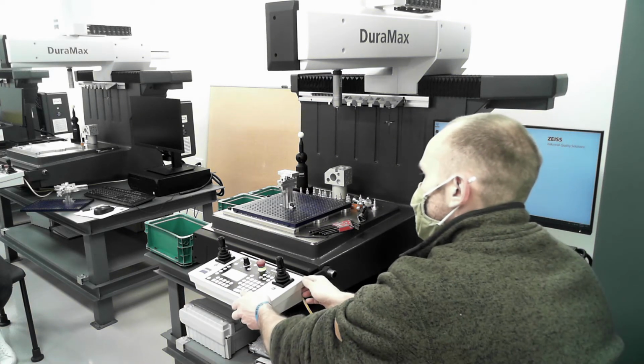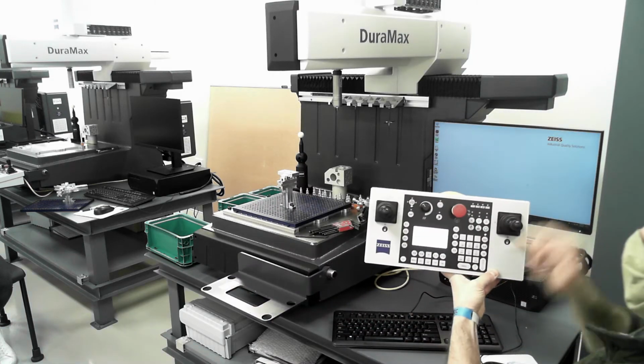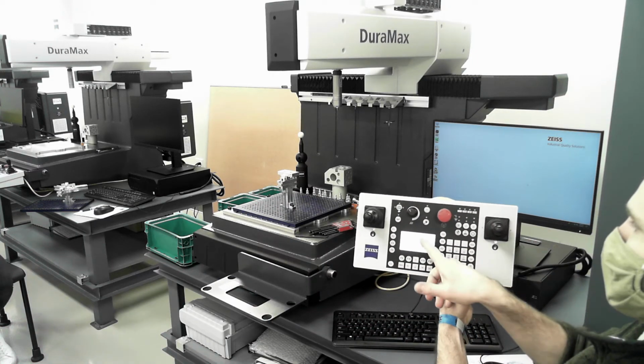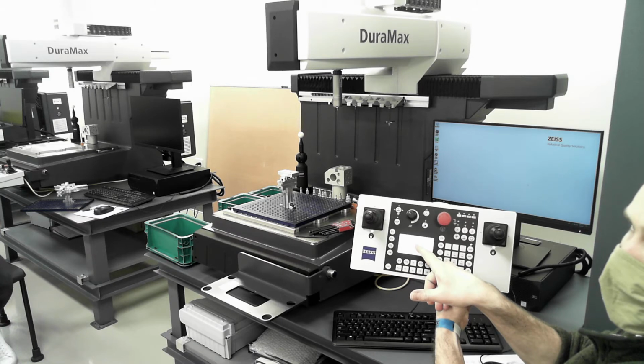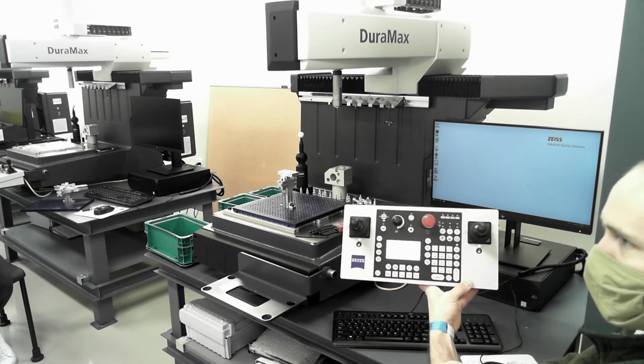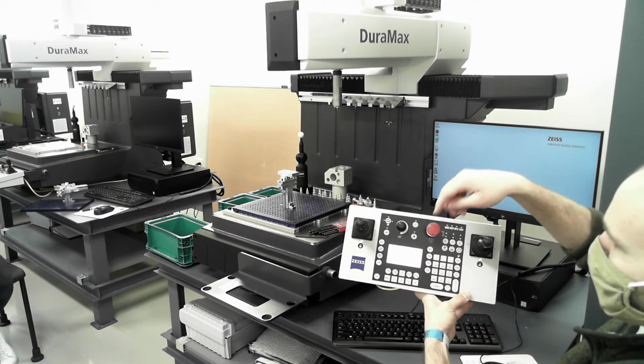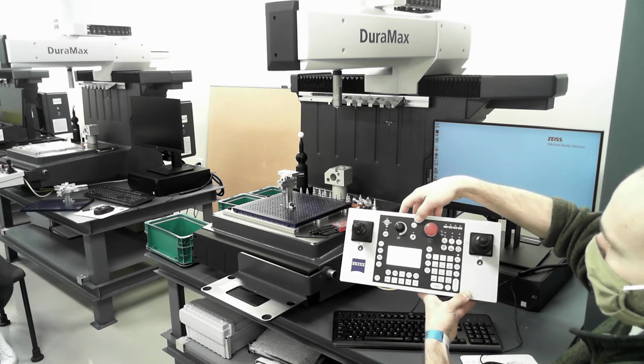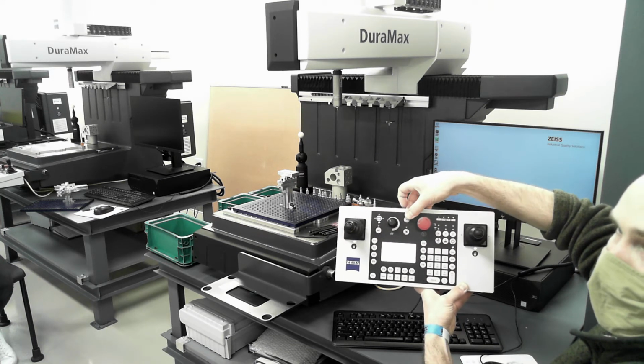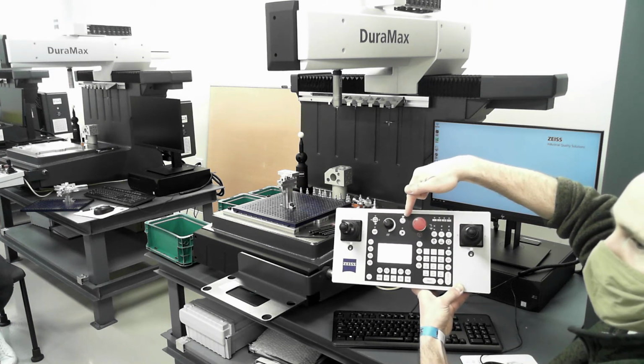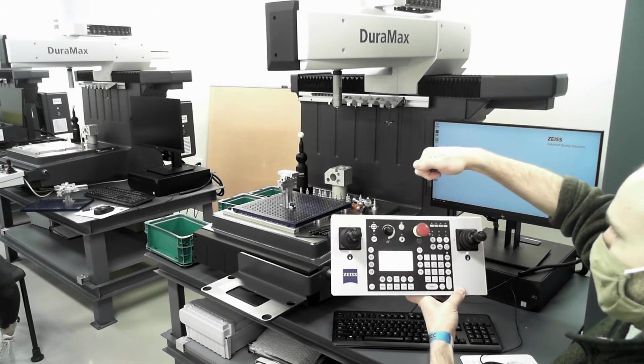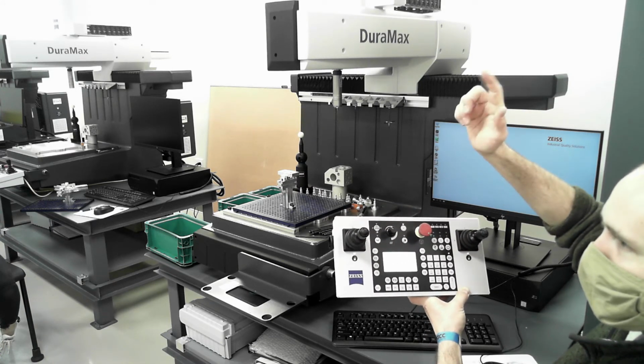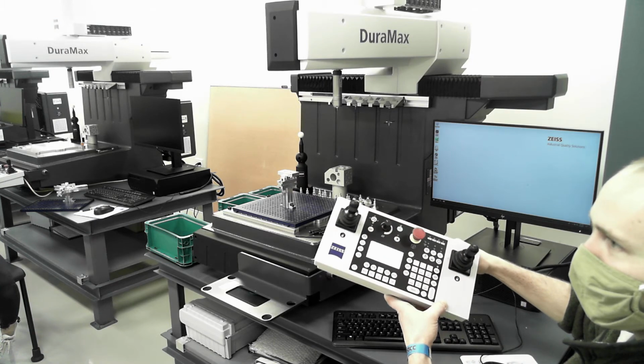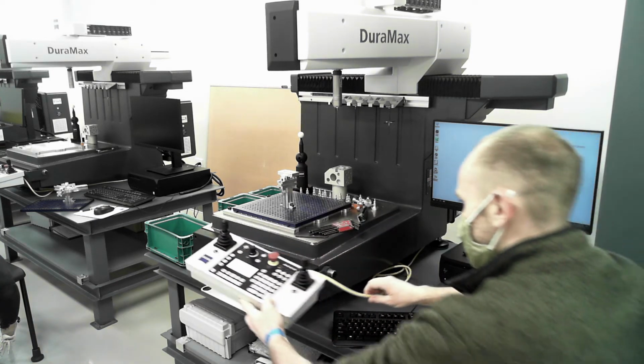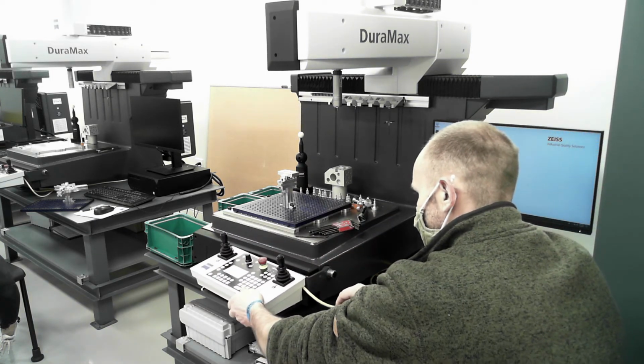Now right here, there's a little icon that was bouncing around on the controller. It said Zeiss, and as soon as I see it say ref, which took about, well, I don't know, what was it, 45 seconds? As soon as I see it say ref, and I see my XYZ readout, I can press this little M button right here. So this M button is the drives on the machine. I'm sure it originated in German, but it's just convenient that the word motor starts with an M. So it's turning on the motors that drive the machine.